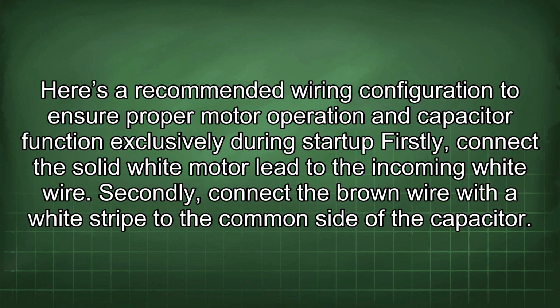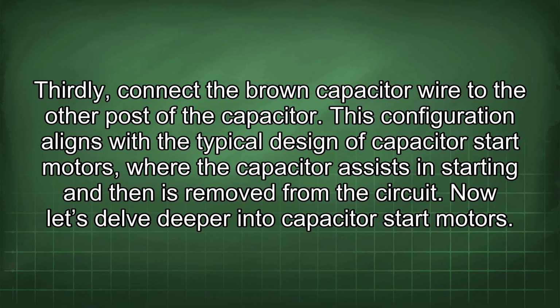Here's a recommended wiring configuration to ensure proper motor operation and capacitor function exclusively during startup. Firstly, connect the solid white motor lead to the incoming white wire. Secondly, connect the brown wire with a white stripe to the common side of the capacitor. Thirdly, connect the brown capacitor wire to the other post of the capacitor. This configuration aligns with the typical design of capacitor start motors, where the capacitor assists in starting and then is removed from the circuit. Now let's delve deeper into capacitor start motors.